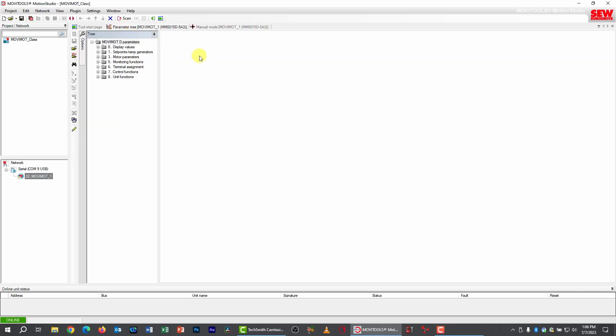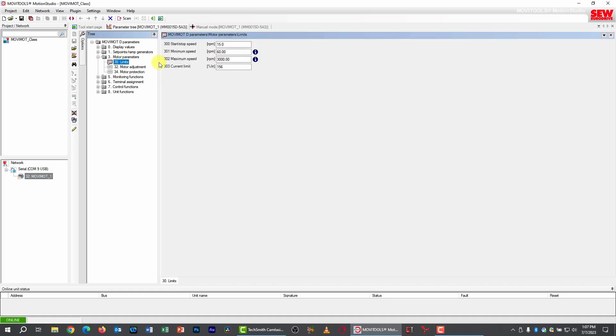And I'll go back to the parameter tree. Now one of the things that you may have wondered about is why did we have those sort of odd minimum and maximum speeds, 60 RPM and 3000 RPM? Well, they come from a parameter in group 3, motor parameters. We haven't really looked at this branch of the parameter tree much. It's subgroup 0 limits, so let's open that up. And you notice we have two parameters, 301 and 302, that are minimum and maximum speed values. They also have those little blue eyes next to them.